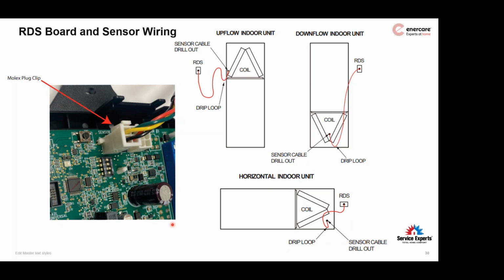What's not pictured here is that loop. You can make it just above the coil drain pan, and it will drip into the drain pan if there was ever any sort of condensation buildup on that sensor wiring before it exits either the ductwork or the cased coil. The Lennox product will come with a grommet to run that wire through from the sensor, so that wiring is protected, whether that be ductwork or cased coil.